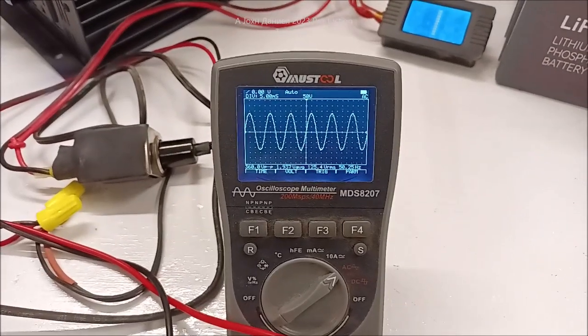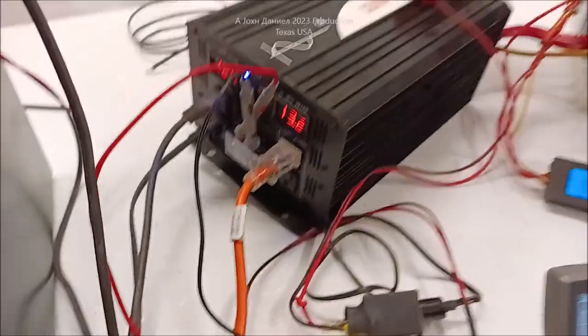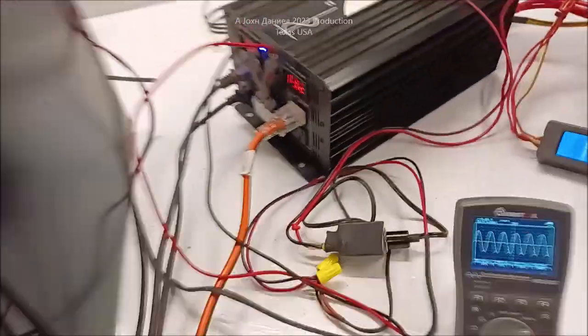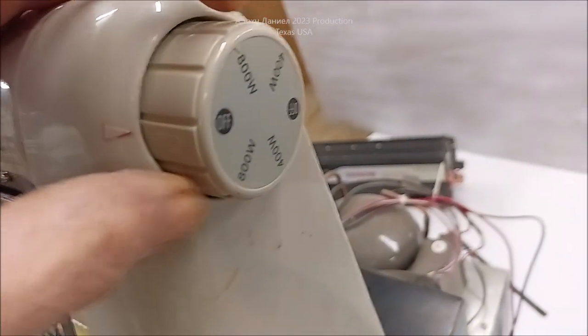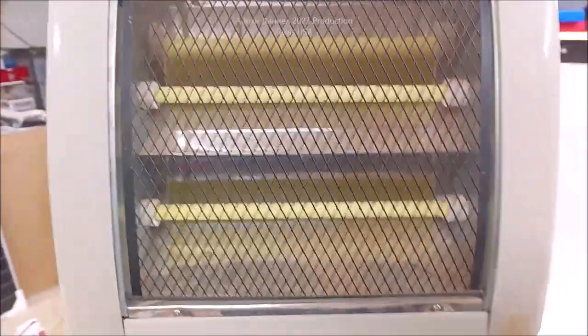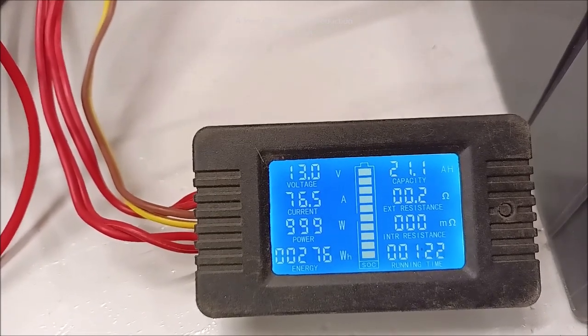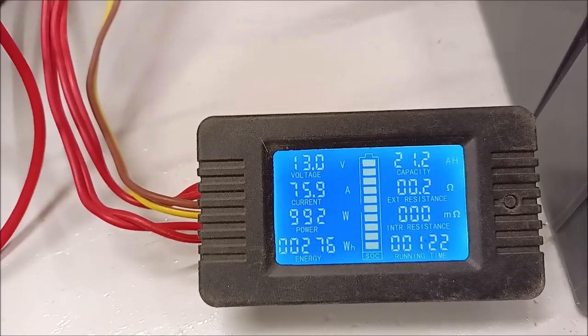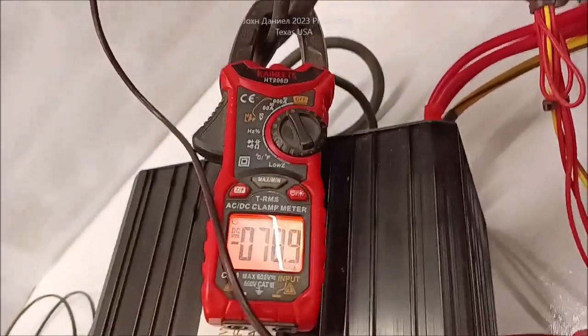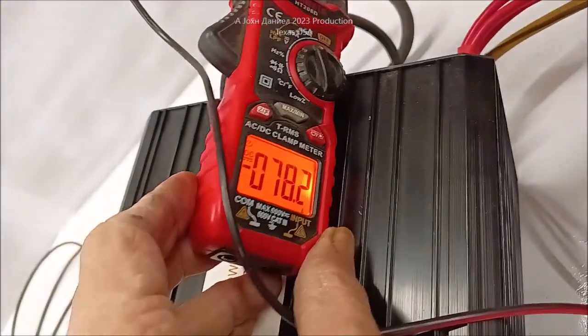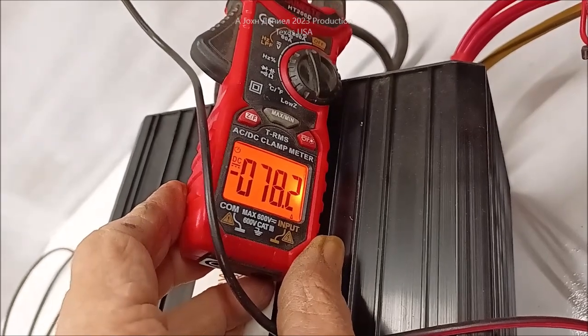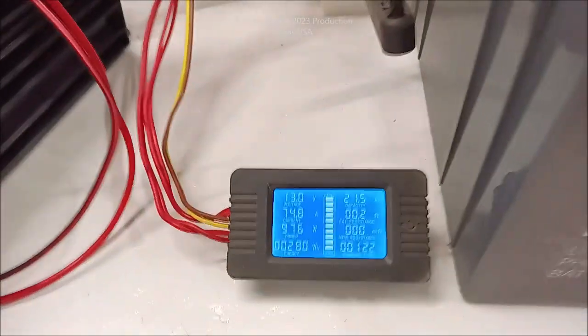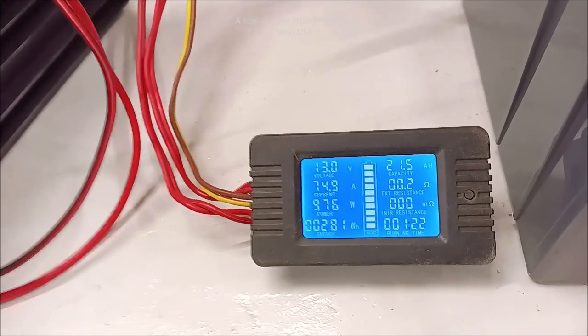And we will look at the voltage. Currently the voltage coming out of there is beautiful pure sine wave. Then we're going to go ahead and start putting on a load. Up here we have, we're going to go 800 watt resistive. We're going to look over here, and now we are pulling 77, 76, so it'll bounce down about 75. It takes a little starter power for that thing. And you're going to look over here, and you're going to see what it's getting. So the line measurements are close, 78. I think we're about three amps off. Voltage still perfect.